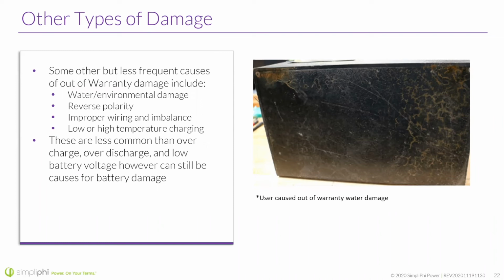While we have our thresholds for low and high temperatures, it's pretty rare. I can think of maybe one or two. I can think of one off the top of my head. I'm sure there's two situations where low temperature, it wasn't actually high, it was low in both those cases, caused the damage, and it really caused a degradation in the battery, not actual damage. These are less common than over discharge, overcharge, and low battery voltage, but they definitely can still be some causes.